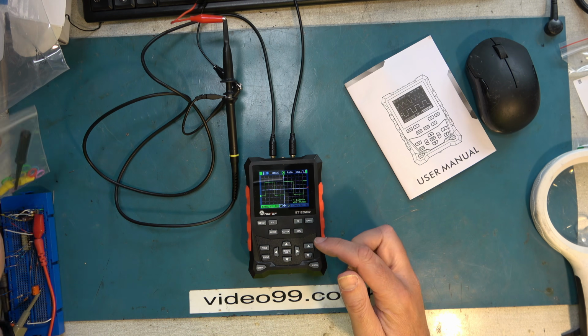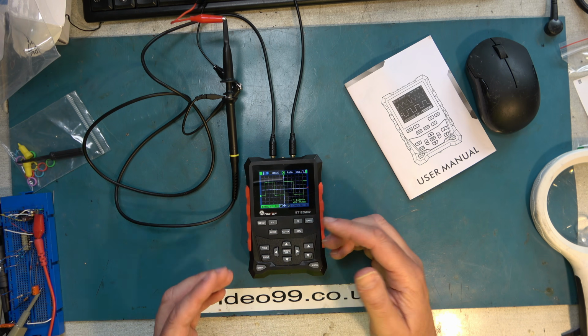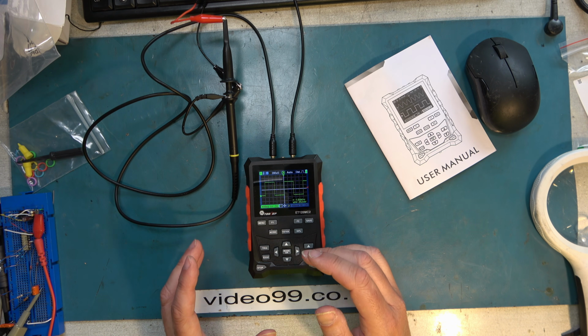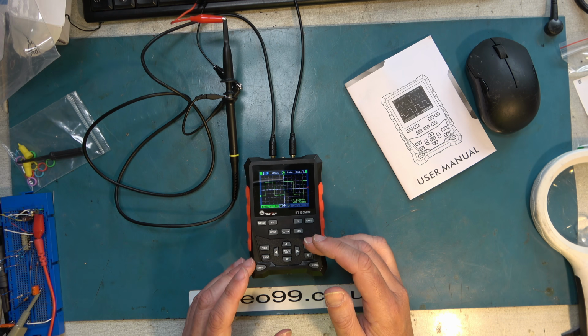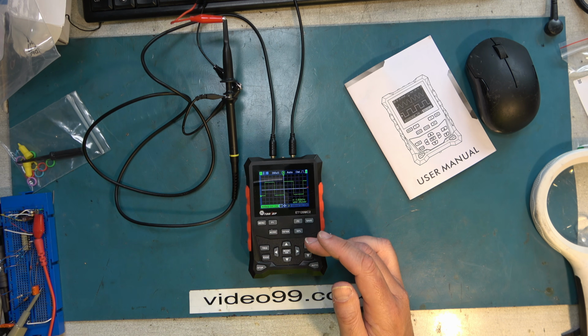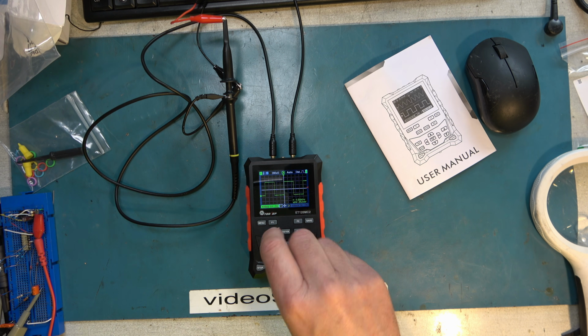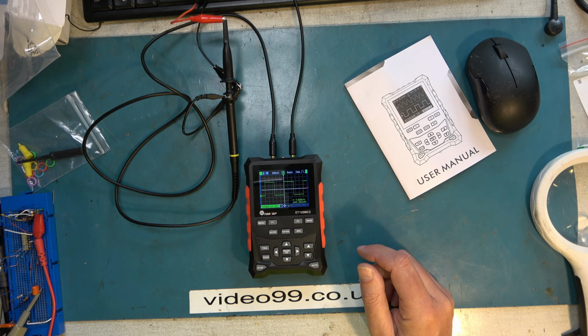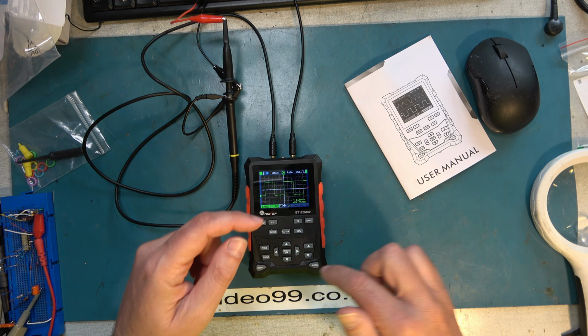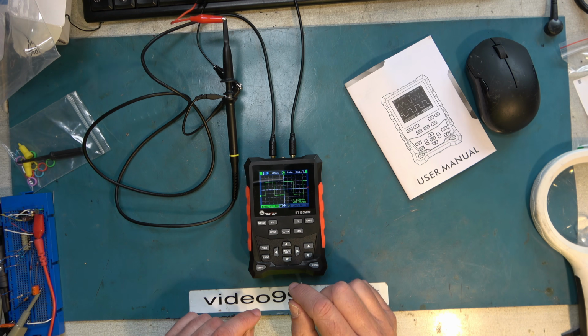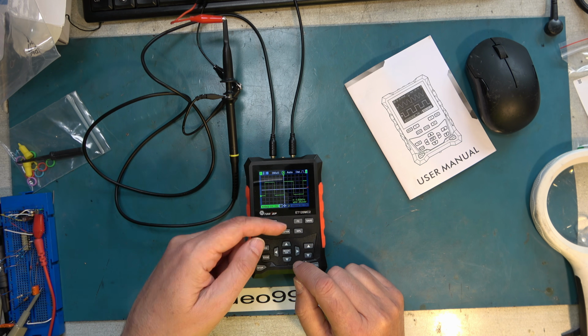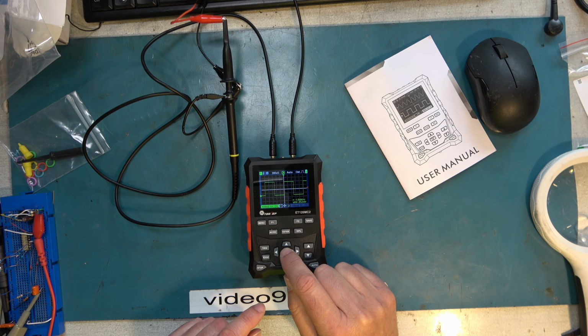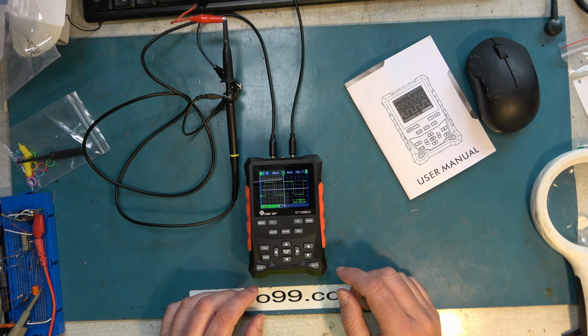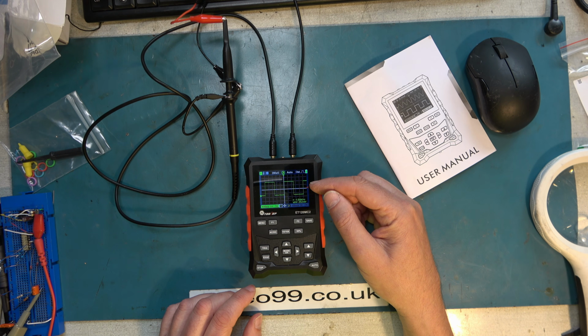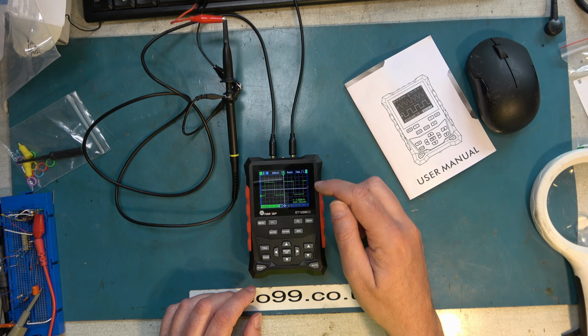There we go. Now it's inevitable, of course, you're not going to have a control for vertical and horizontal position, and a control for gain, and a control for sweep, as nice little rotary encoders on something this small. You're inevitably going to have to use buttons, so you just need to keep an eye on that center marking there between those two modes. But we've got that set up nicely now. The red mark there is the trigger level, so that's set to 50%.